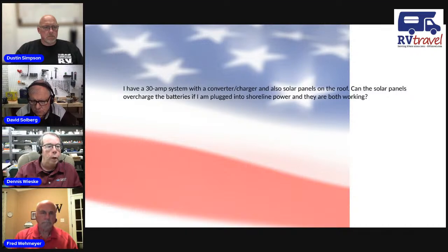It really depends on what mode the solar panel's profile is in. After a period of time, the charger will drop down to a storage voltage. Usually what we see is people in the morning, those solar panels power up, charge at a high rate, and then drop down lower. Running 13.6 every once in a while shouldn't hurt the battery, and you do want to maintain those batteries, so it shouldn't be a problem.